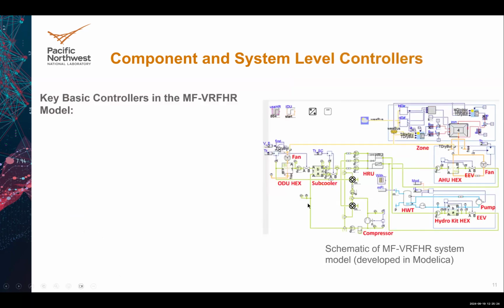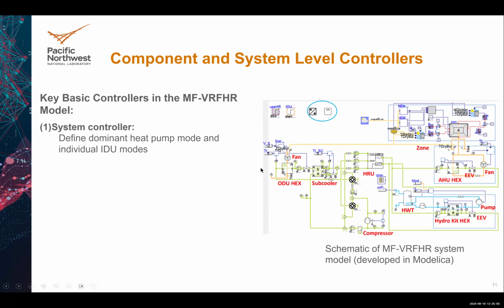So next, I will start with how we build controllers for this system. Control is very important, right? Even if you have the model, if you do not have control, you cannot operate the model for different operation modes. So following the same way, I will introduce some critical controllers we use. For example, the first one is the system controller. This controller defines the dominant heat pump mode and the individual indoor unit modes, like here in the Modelica.